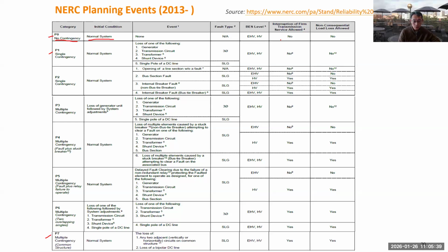So the planning engineer needs to study any normal system change without loss of any element of the system. That is called P0. Starting from P1, P1 is a single contingency. A single contingency is based on the normal condition, and you can just lose a single generator, single circuit, single transformer, or single shunt device. The fault type can be three-phase or a single line to ground, right? So you really need to study on the high voltage, usually meaning above 200 kV, and EHV means usually the voltage above maybe 300 kV.